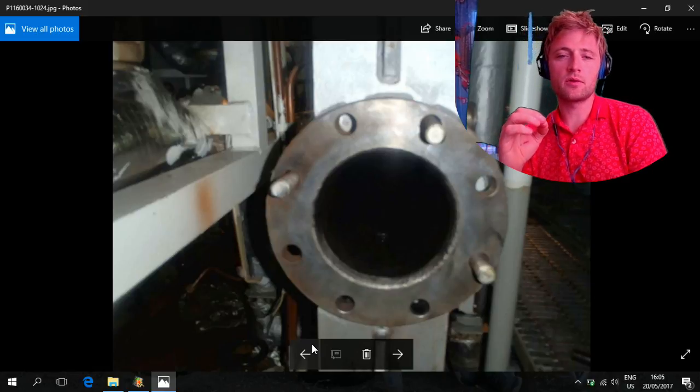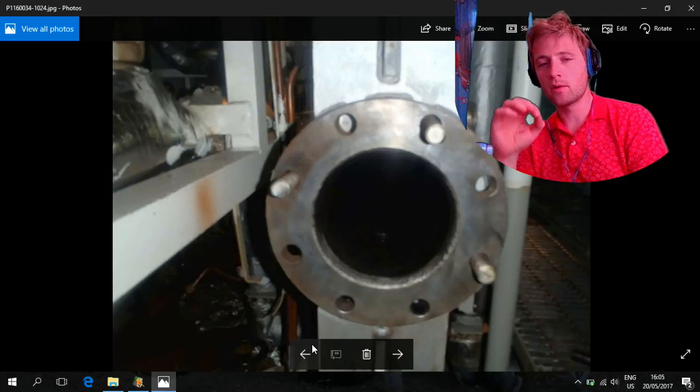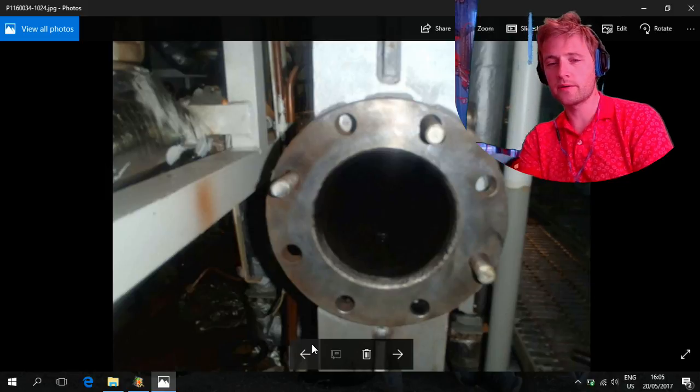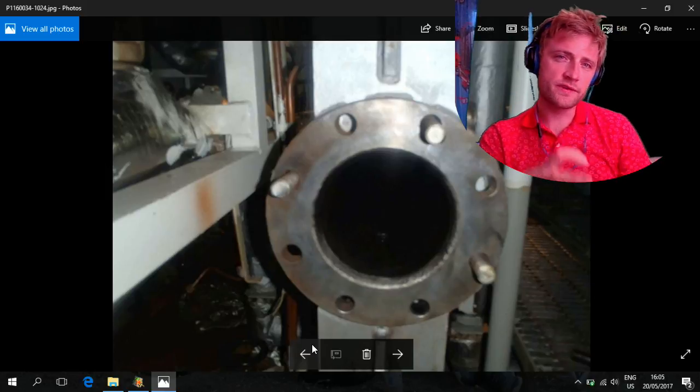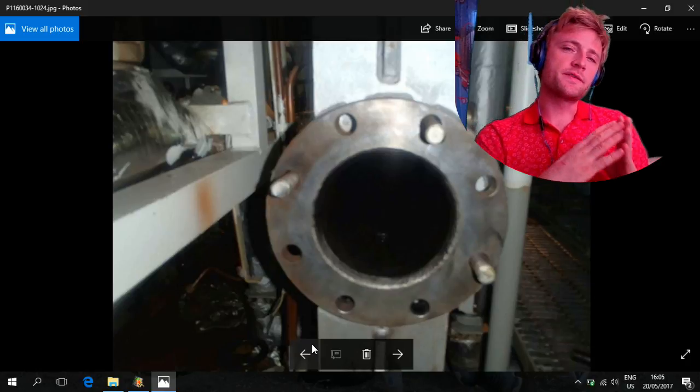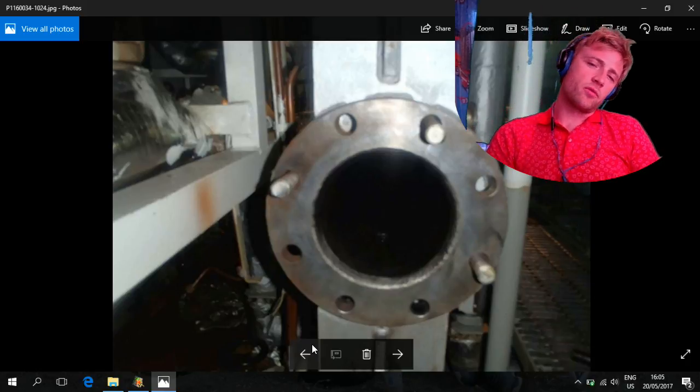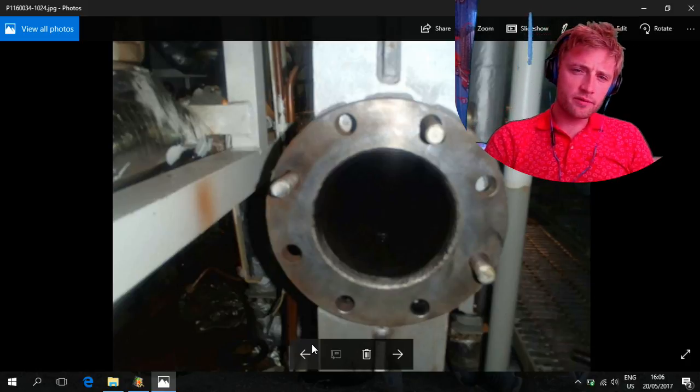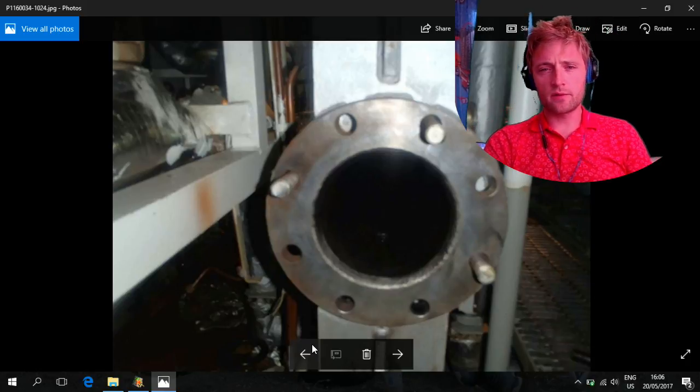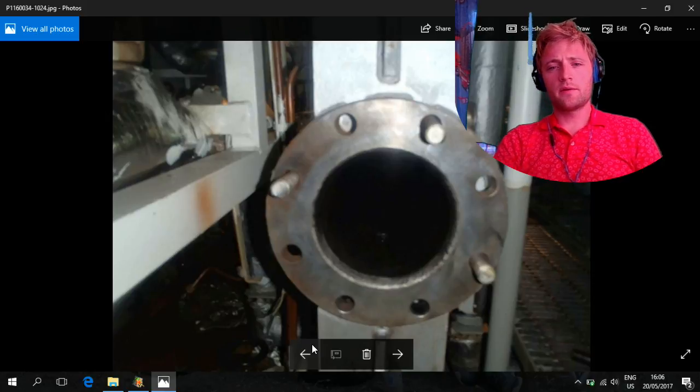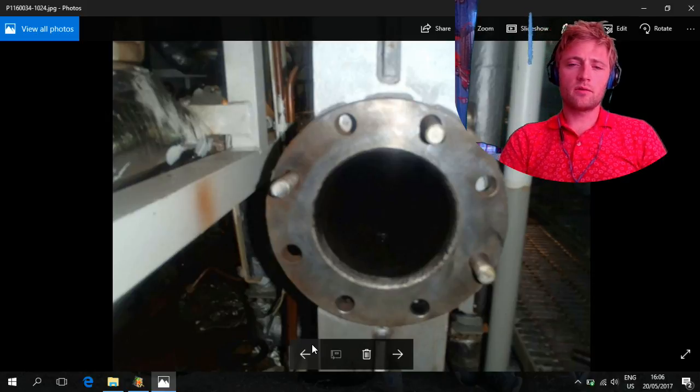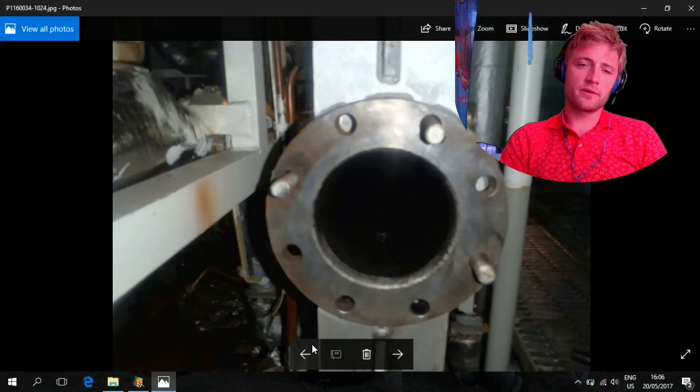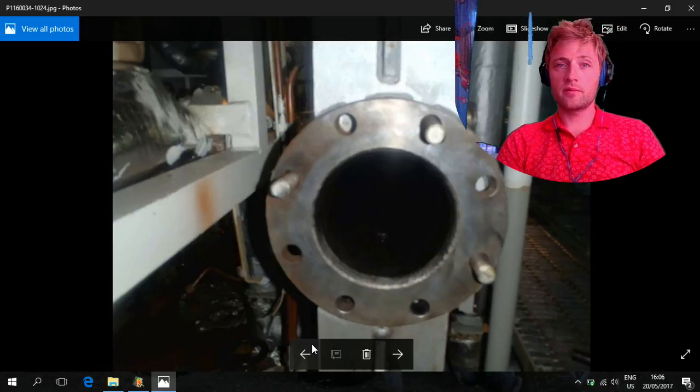Just slowly to heat all the metal parts, because as you know, steam from the boiler is coming with 170, 150 degrees, and the metal is cold, it's 40 degrees. It's environmental temperature.